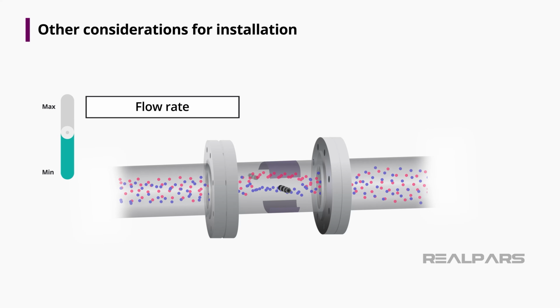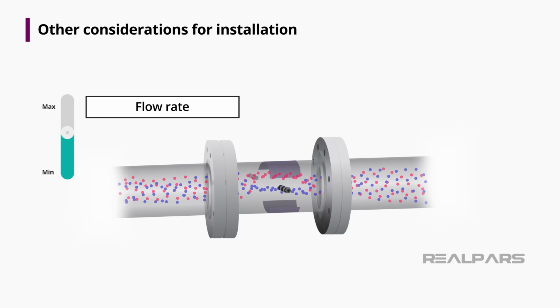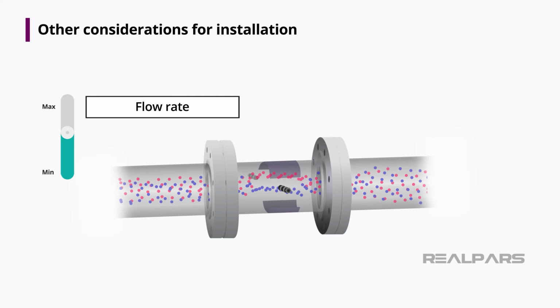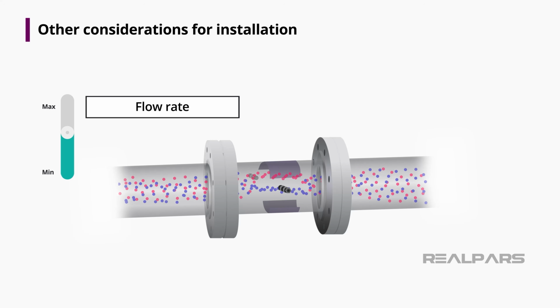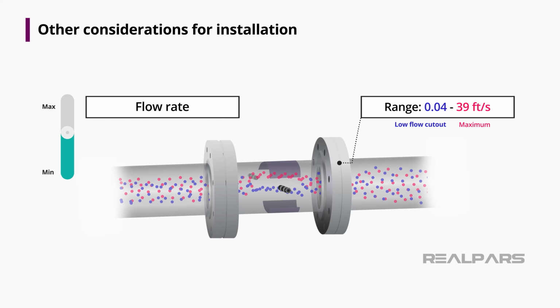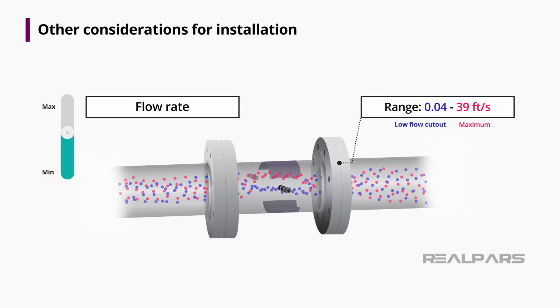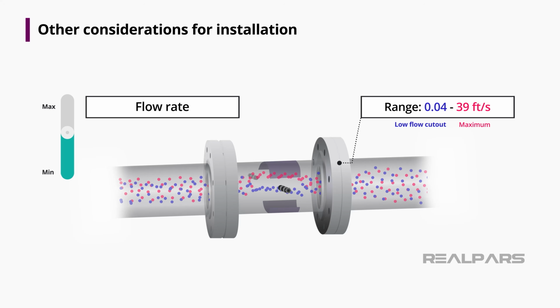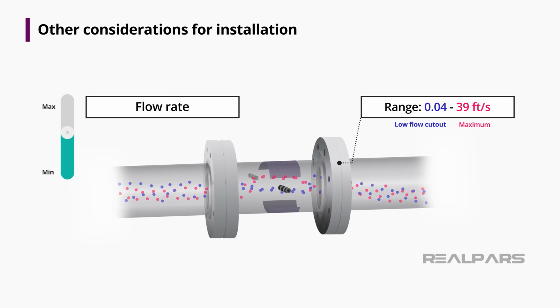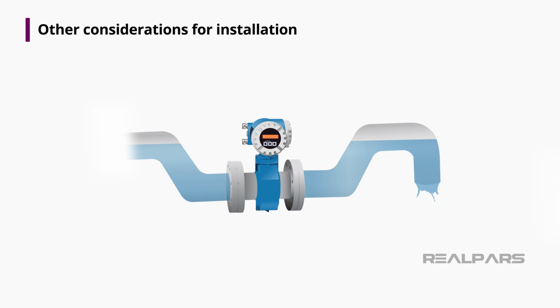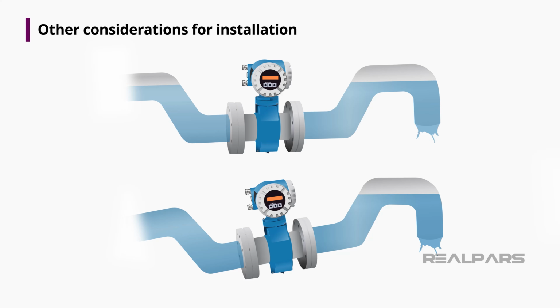Knowing the minimum and maximum flow rates for your process can help determine the range of flow a specific mag meter model will be able to measure. Each model has a low flow cutout point and a maximum velocity that can be measured accurately. If the pipe will not always be full of fluid, flow accuracy will be affected. It might indicate the meter needs to be installed at a low point in the pipe, or in an upwardly sloped pipe run to ensure a complete fill during operating conditions.